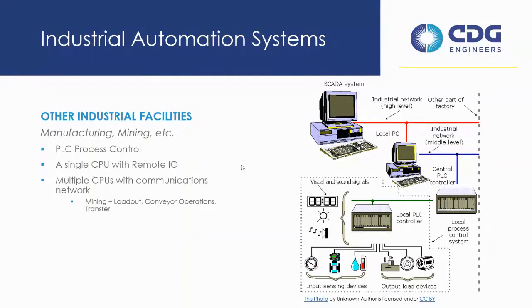Our background is typically in mining, so you might have a PLC system that controls your loadout, your conveying operations, and your transfer. But the PLC systems don't necessarily all have to communicate back to a central location to operate it. It's not a giant process. They can operate independently of each other. So your transfer operations can just take a hardwired input or two or a dozen from like a belt trip or a speed switch from the conveying system up above and tell it when to operate or when not to operate. Same with your loadout. It can just operate independently of the conveying system that feeds it. They don't necessarily need to all operate in unison as one.